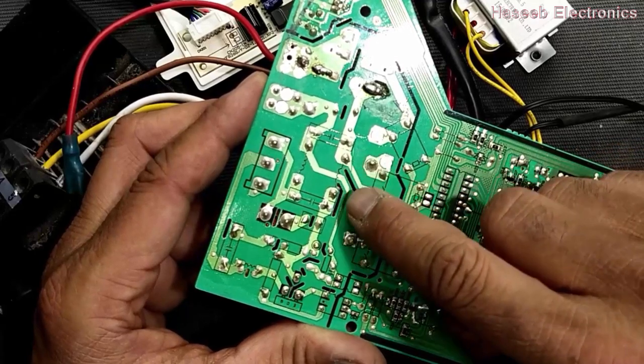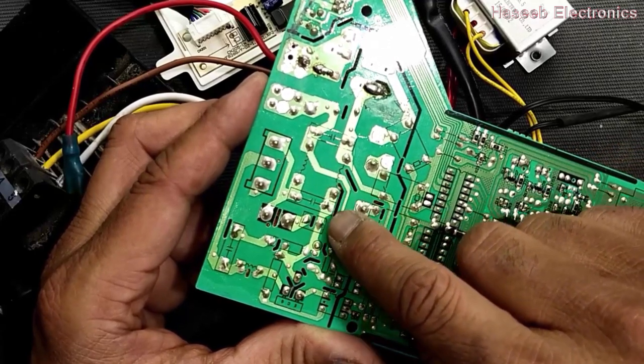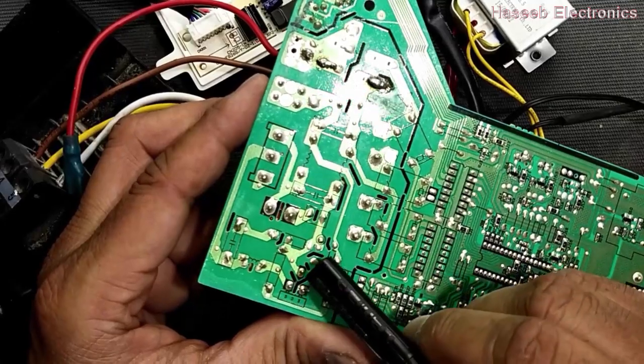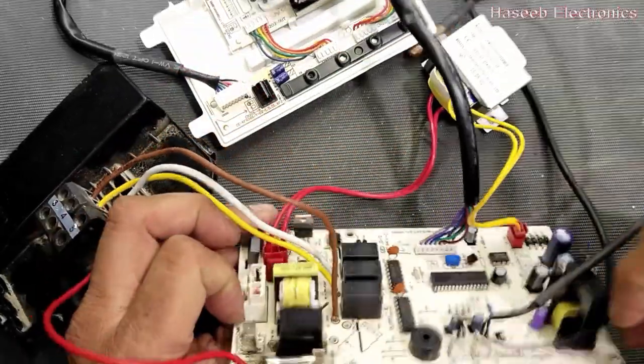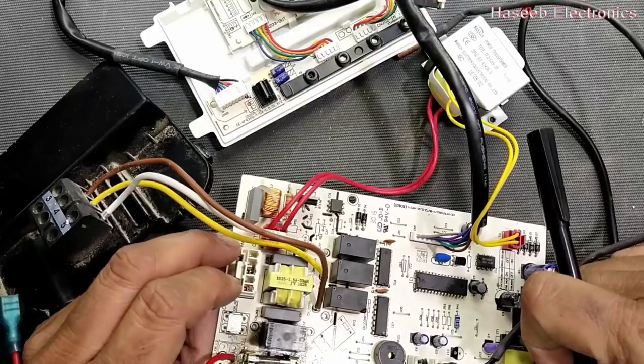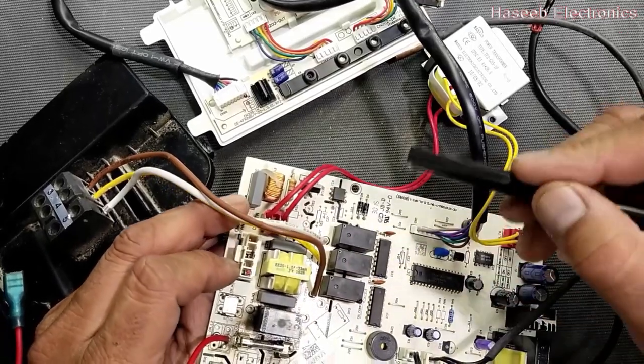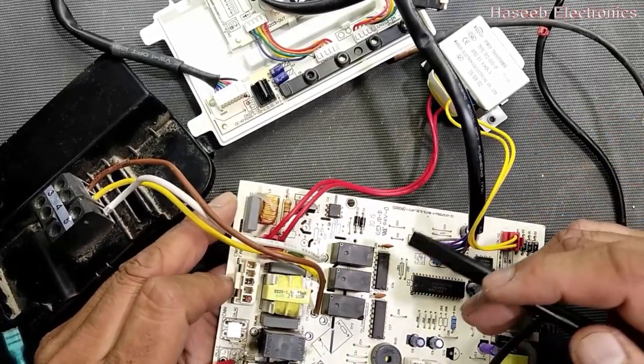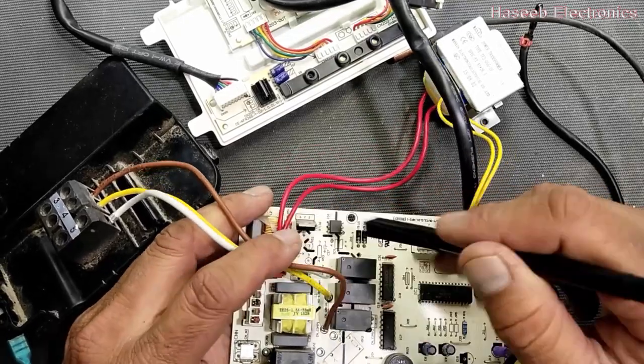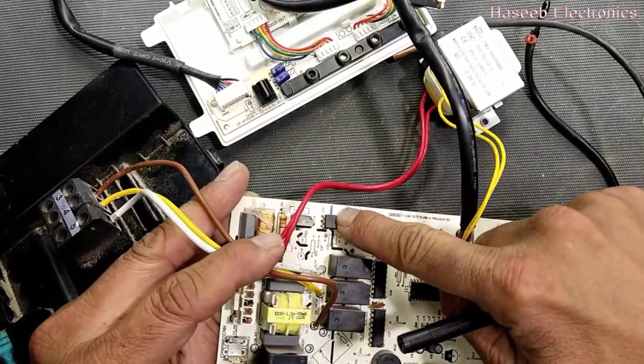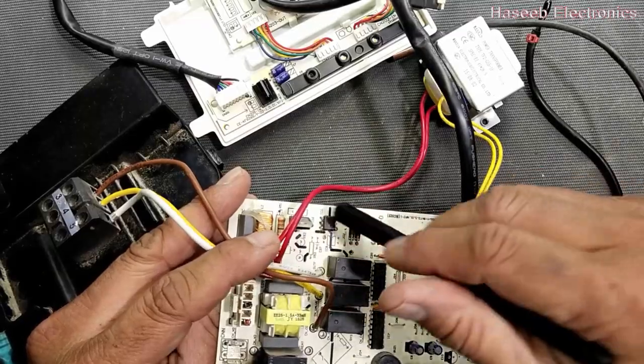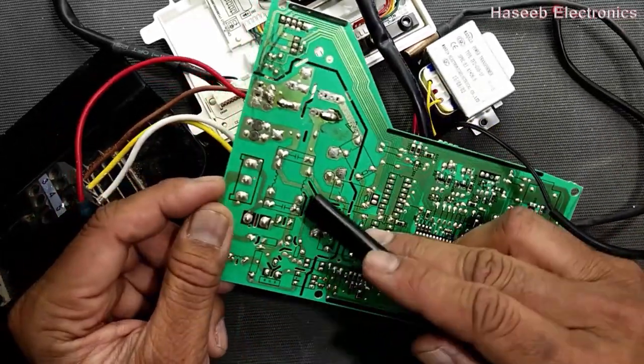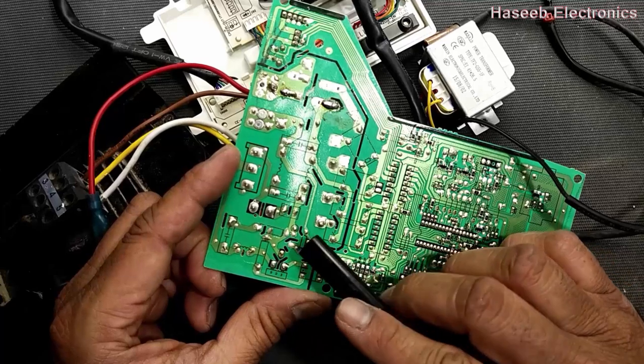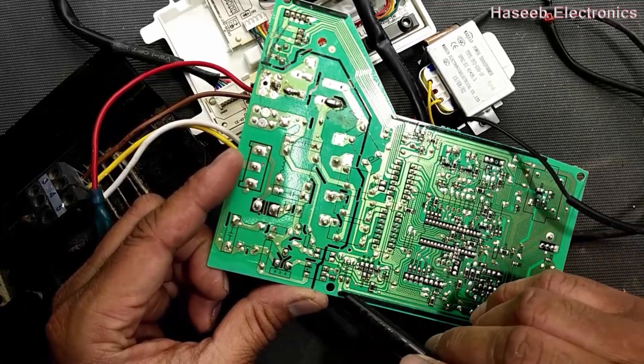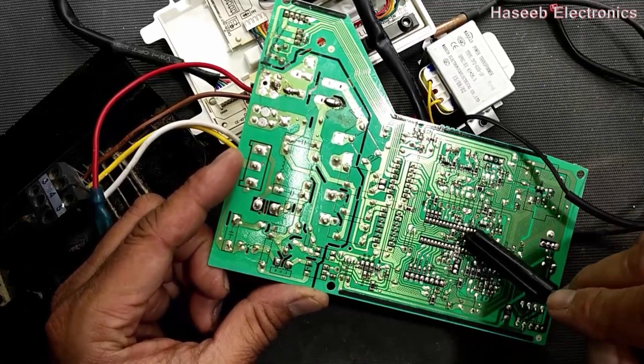This line, after passing through the fuse and the inductor, goes to the triac. This indoor blower fan unit does not have high, low, medium speed relays. It has just this triac, and the triac is controlled by this optocoupler, and the optocoupler receives a drive signal. It is a phase drive network. It takes its drive from this microcontroller.